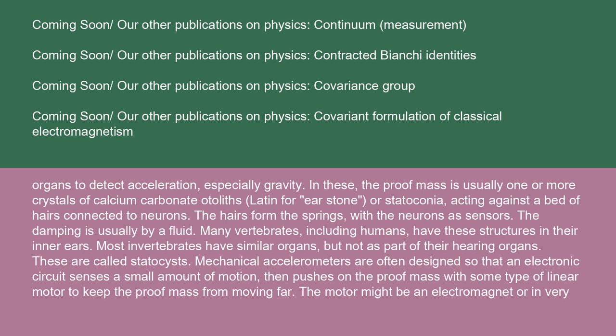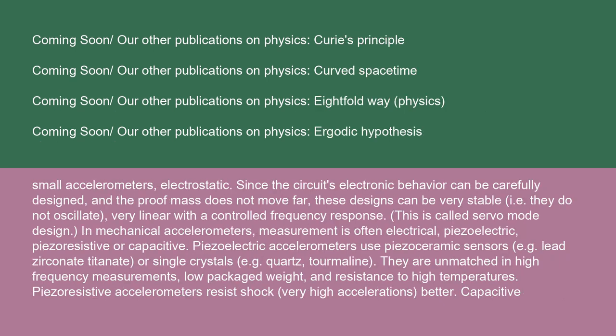Mechanical accelerometers are often designed so that an electronic circuit senses a small amount of motion, then pushes on the proof mass with some type of linear motor to keep the proof mass from moving far. The motor might be an electromagnet or, in very small accelerometers, electrostatic. Since the circuit's electronic behavior can be carefully designed and the proof mass does not move far, these designs can be very stable — they do not oscillate — and very linear with a controlled frequency response. This is called servo-mode design.